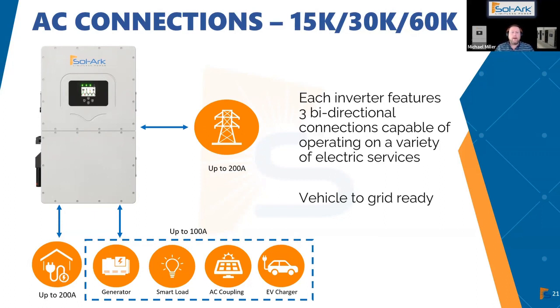So each of the inputs on the inverter can go either direction. We have the option for the gen port in particular to use a generator. We can use a smart load option. This is all software driven. Essentially, the AC coupling can go into the inverter there on the gen port, and you could put an EV charger. So you could just run, say you had a canopy with small container batteries, one line out to the grid side of the inverter, and you could connect your EV charger directly off of that gen port, and then have another port that's rated up to 200 amps and allow you to limit your wire runs out to those canopies.